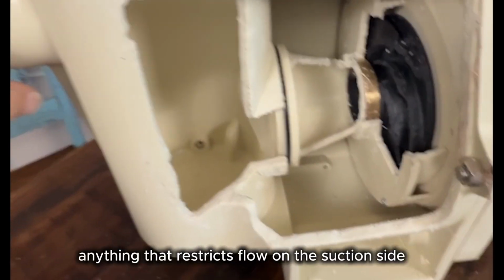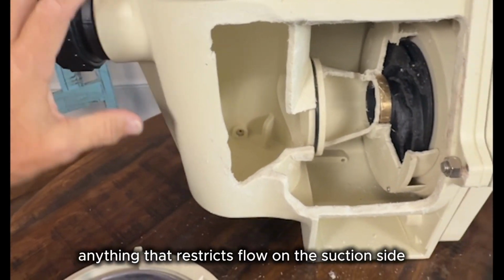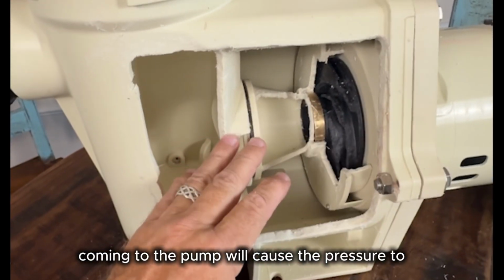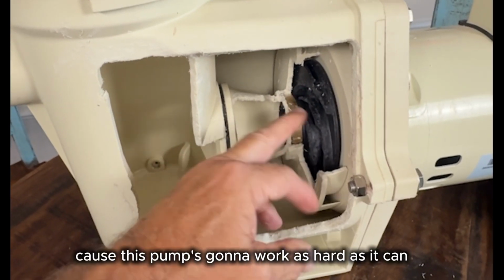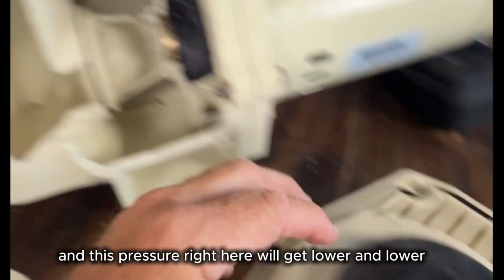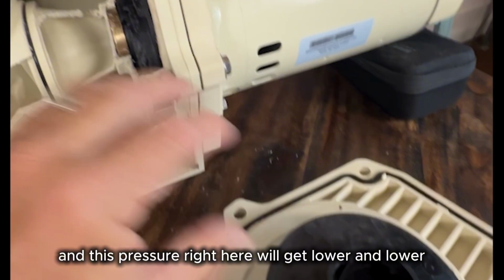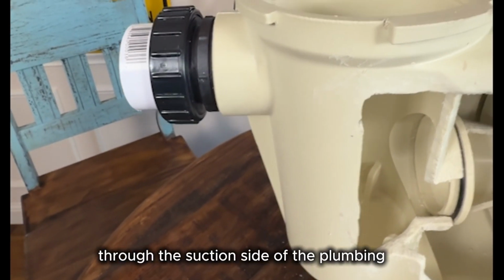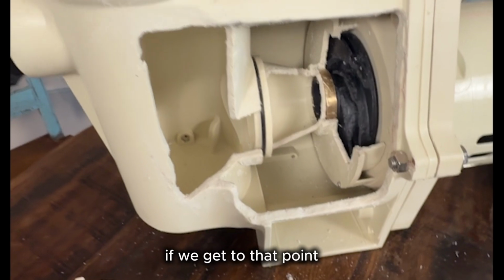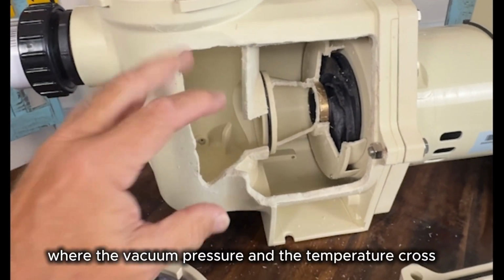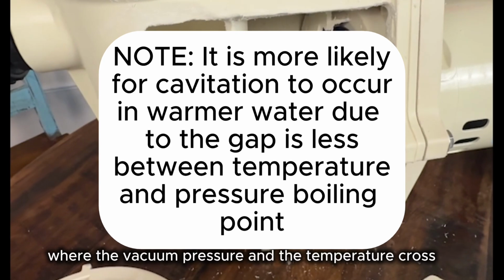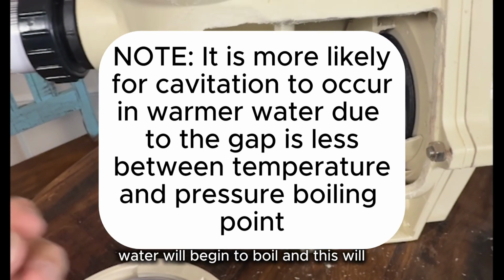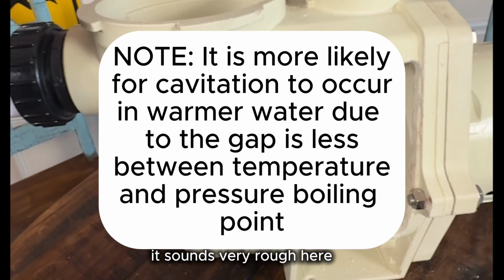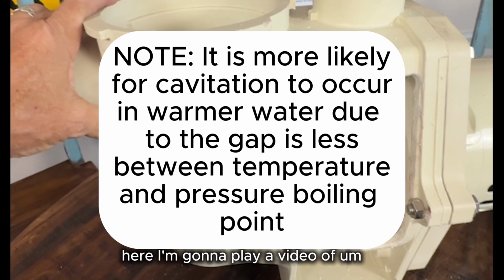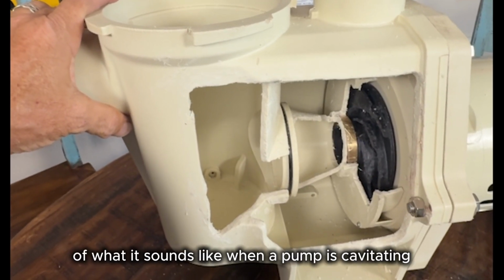Anything that restricts flow on the suction side coming to the pump will cause the pressure to get even lower at the pump, because this pump is going to work as hard as it can, and this pressure right here will get lower and lower and lower, and that will transfer through the suction side of the plumbing. If we get to that point where the vacuum pressure and the temperature cross, water will begin to boil. You typically will notice it because, first, it sounds very rough. Here, I'm going to play a video of what it sounds like when a pump is cavitating.